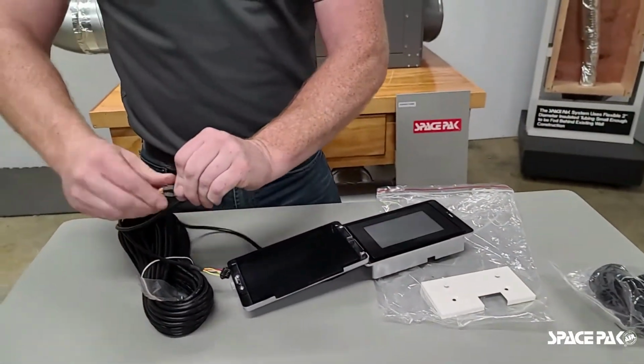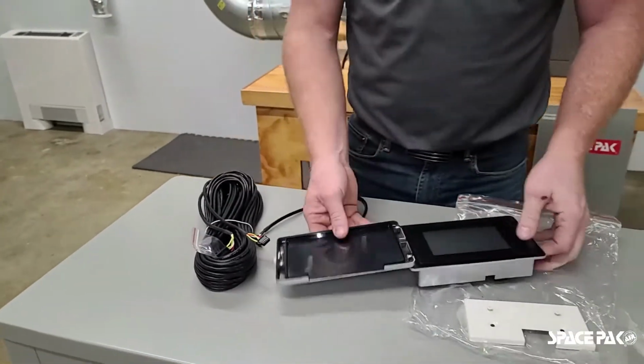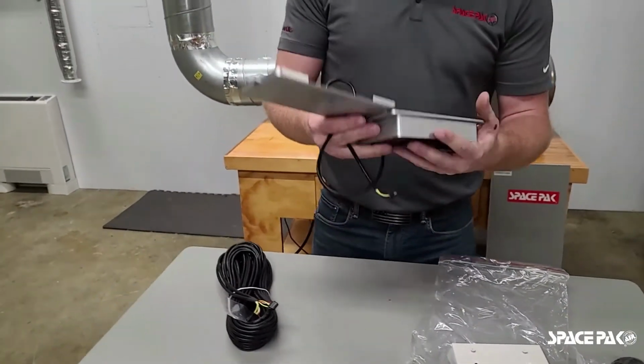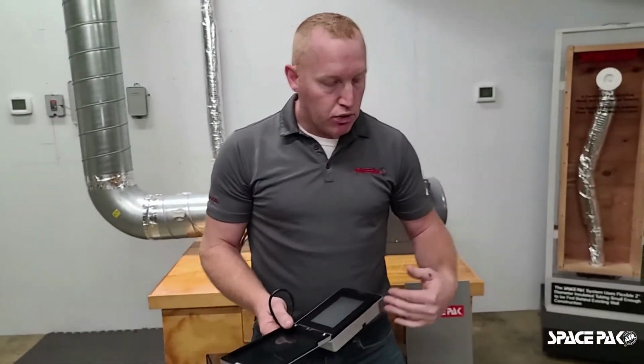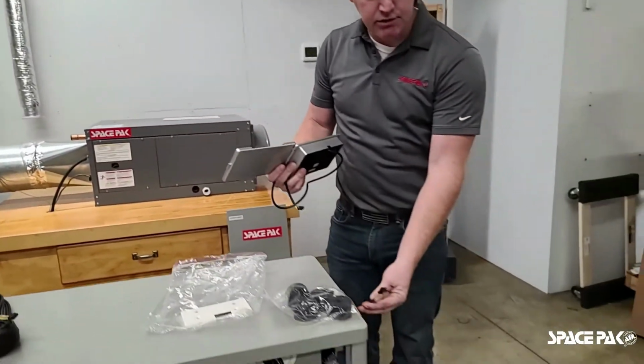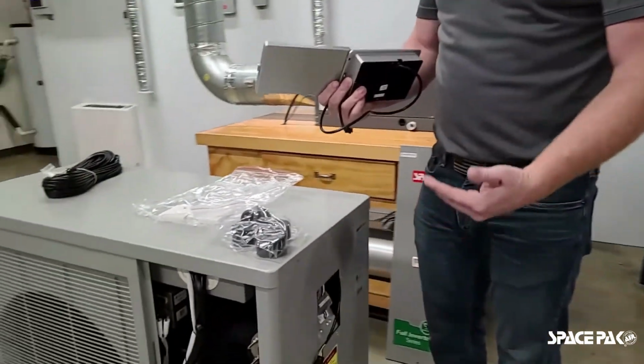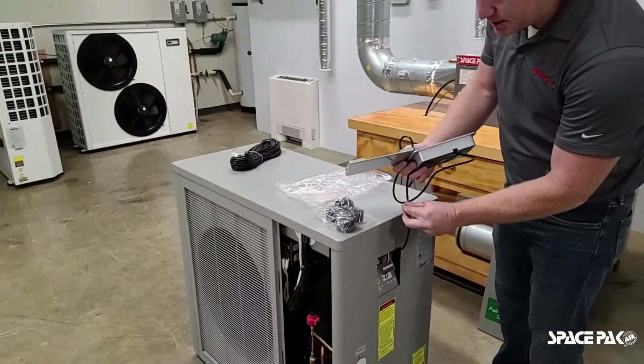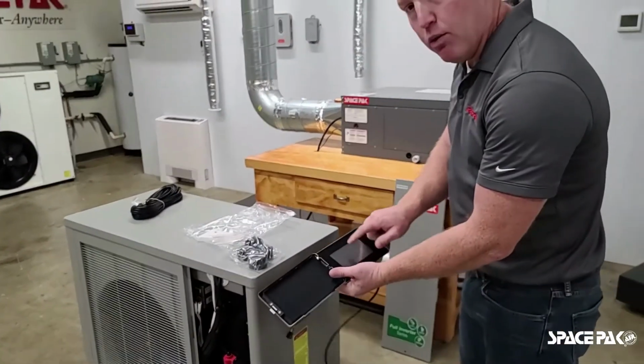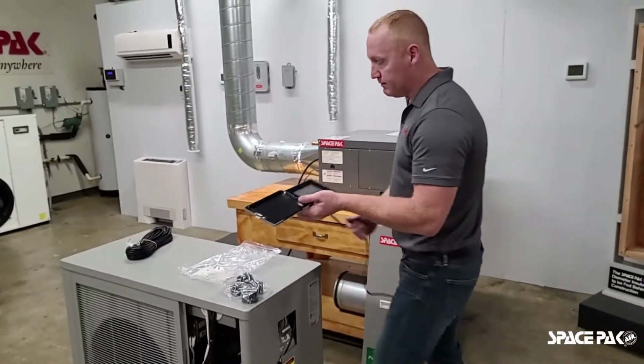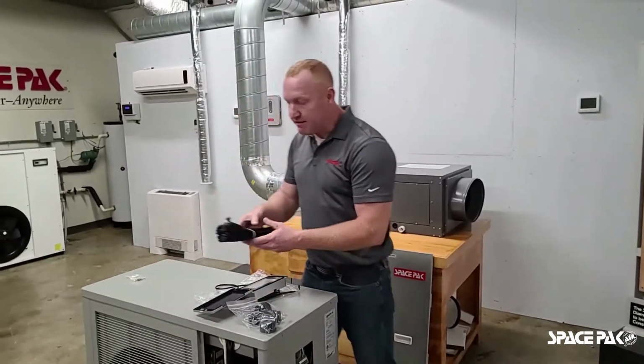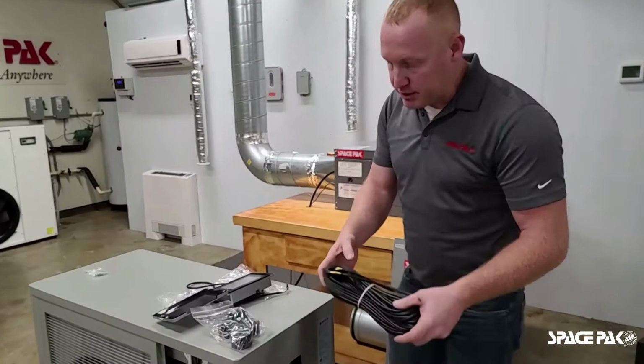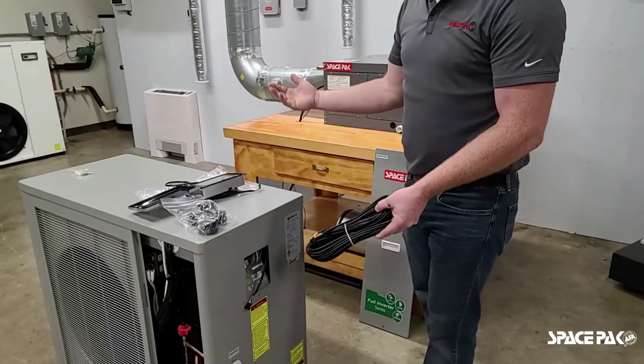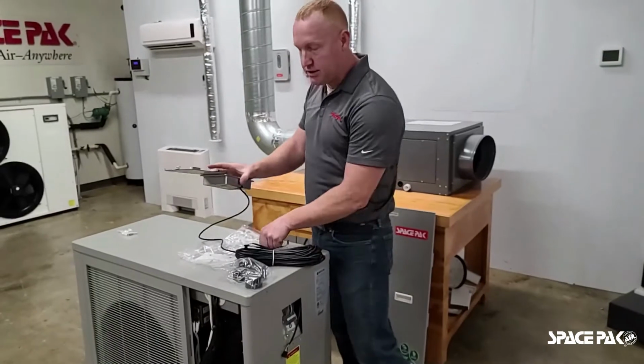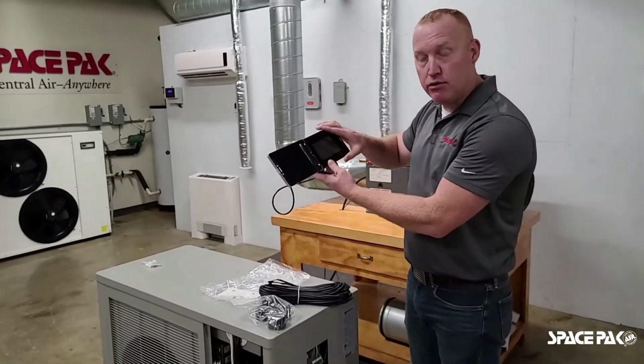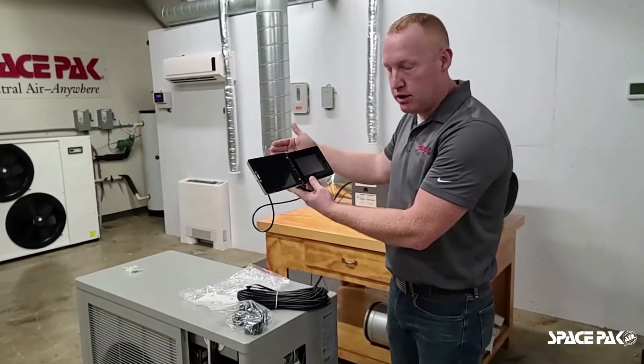We can separate it. One of the great features here is that our control unit, we can essentially take it and carry it with us. So we mentioned earlier, we have the connection for control here to the left. If we were working outside with the unit, we can plug in this connection here and make adjustments to the unit while we are outside. We could also take the supplied 65-foot cord, hook into this unit, wire back to the mechanical room, take this control with us, in turn mounting it back in the mechanical room and be able to make adjustments while we are in the boiler room.